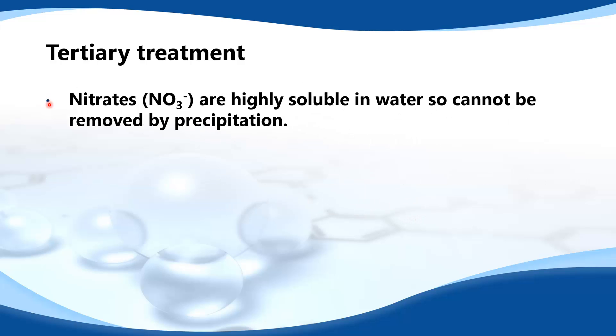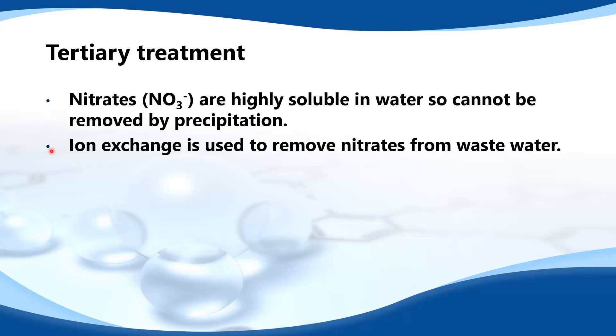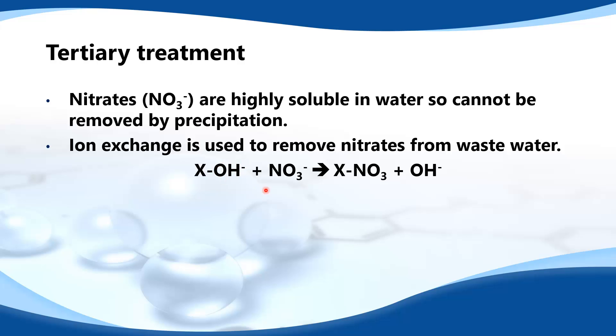Nitrates are highly soluble in water, so cannot be removed by precipitation. Ion exchange is used to remove nitrates from wastewater. Here's an example of ion exchange where the hydroxide ion, the OH- ion, is exchanged with the NO3- ion, the nitrate ion.